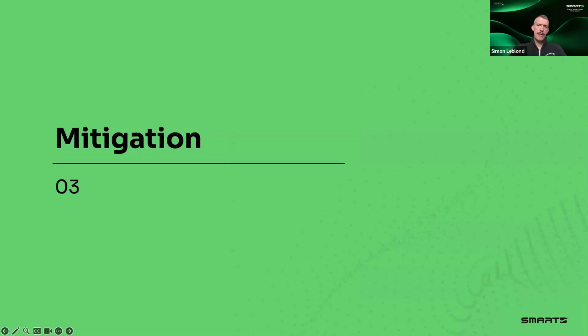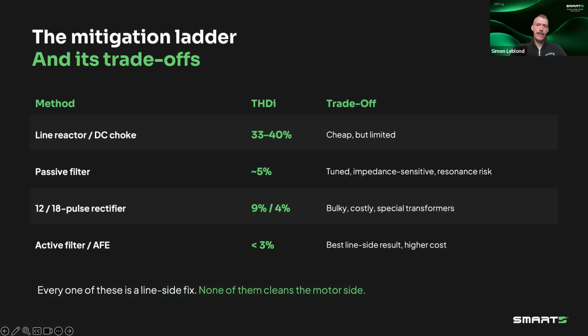So what does typical mitigation look like if we go up the ladder of solutions? As I said, most modern VFDs today will have a DC choke, so they'll bring that 70% harmonic down to 30, 40%. You could also put an external line reactor on top of that and bring it down to 25 or 30%. If you want, you can go to a passive filter, which will get you to the 5% mark. But there is a risk that isn't always discussed.